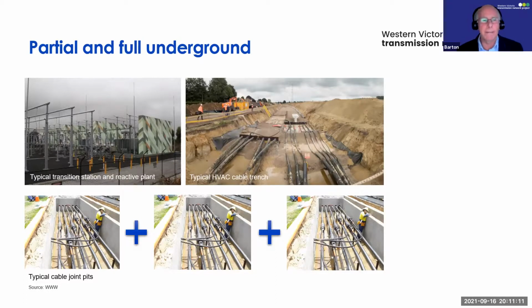I can give a very broad indication of the cost, and it relates to the voltage. With HVDC, you don't need reactive plant because there are much less losses with HVDC, and that's why it's typically used over very long distances. For example, Basslink is around about 385 kilometres, Marinus Link will be about 360 kilometres, and some of the interconnectors in Canada and Europe are up around 700, 800, 900, 1200 kilometres. So typically that's where HVDC is used.